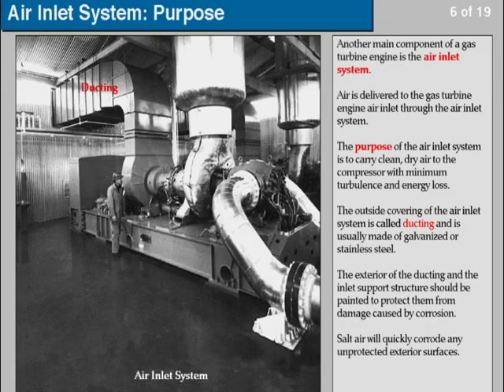Another main component of a gas turbine engine is the air inlet system. Air is delivered to the gas turbine engine air inlet through the air inlet system. The purpose of the air inlet system is to carry clean, dry air to the compressor with minimum turbulence and energy loss. The outside covering of the air inlet system is called ducting and is usually made of galvanized or stainless steel.